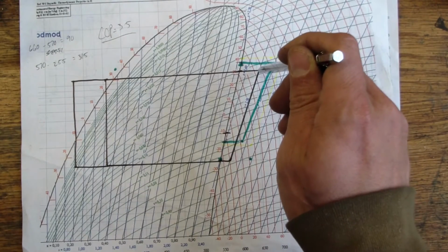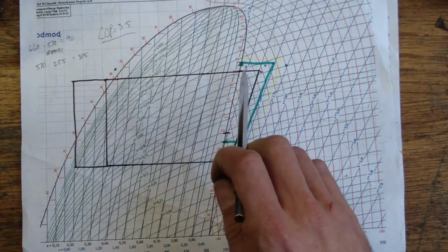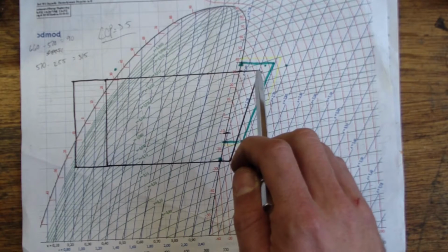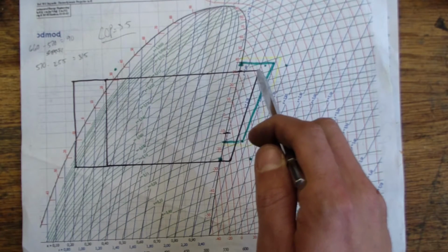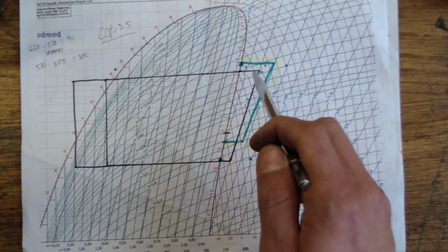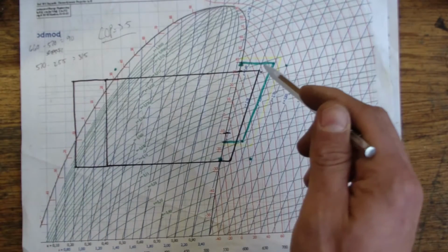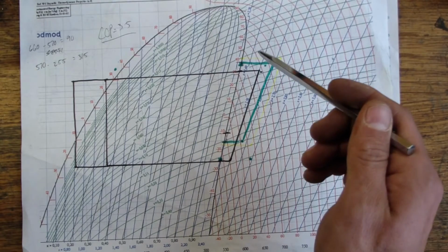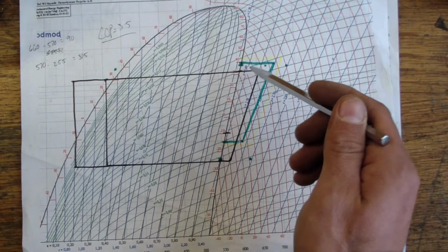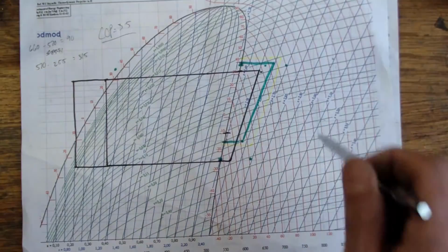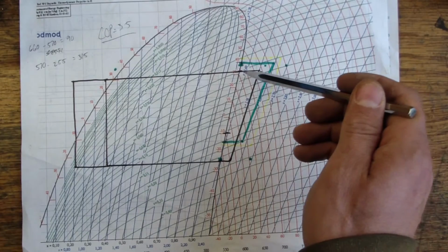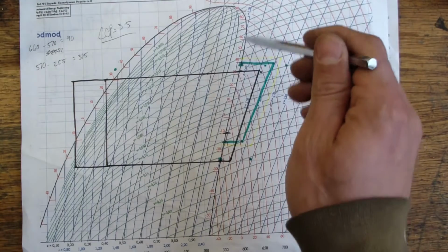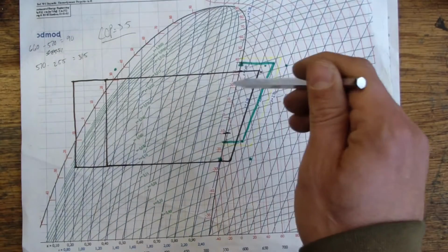So, discharge of the compressor, we're way up here, we're nice and hot. We're nowhere near the saturated vapor curve. So we're more of a rarefied gas, but we're at a higher pressure and a higher temperature. So it discharges the compressor, and it exits the compressor at more or less a constant pressure at the high side, the head pressure level. Upon leaving the compressor, it immediately starts to cool, and we start to cross back over some of those lines of constant temperature, the isothermal lines, and we're cooling that slightly until we reach the point of the saturated line, on the saturated vapor line on the saturation curve here.